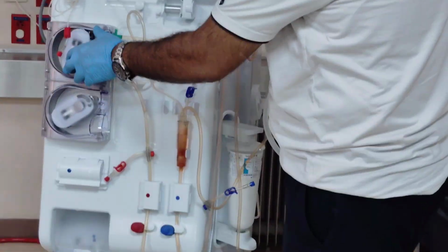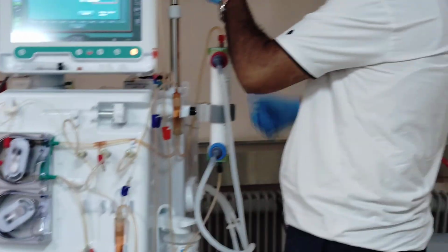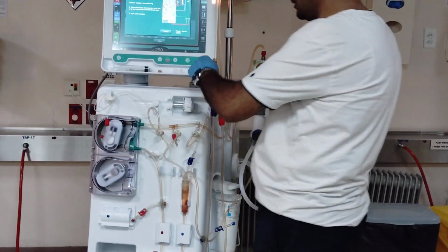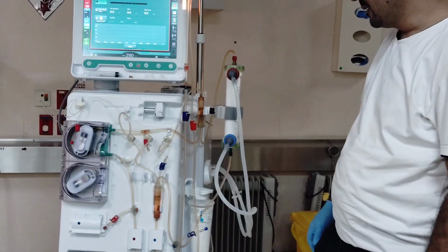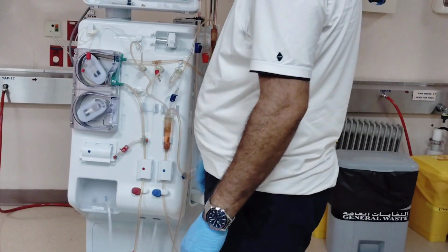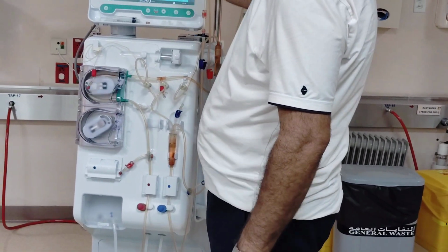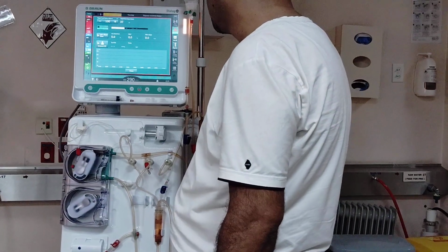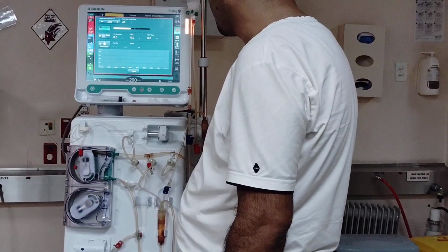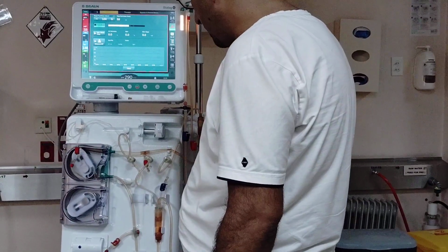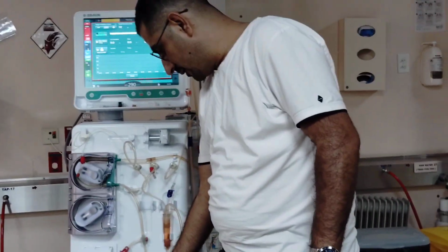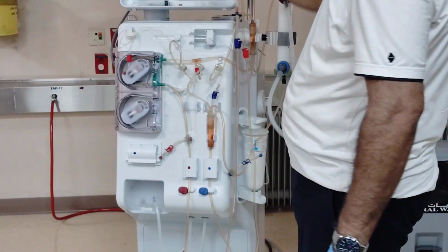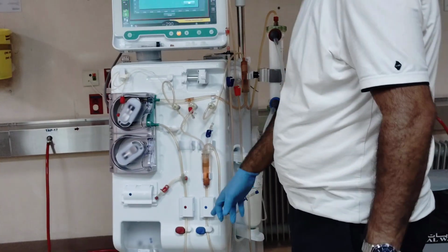Now the blood pump will stop to give you a chance to open the IV set. Yes, with this clamp. After you open it, you can press here, and now the system will start to give a bolus of up to 100. And there is no need to close any clamp, because you can see this one is now closed already.